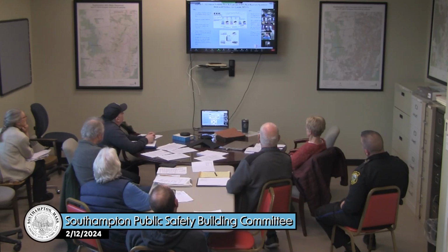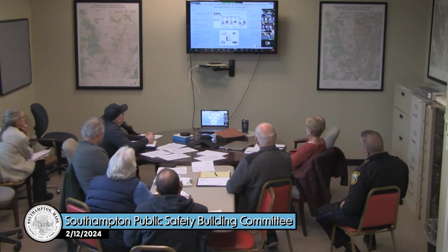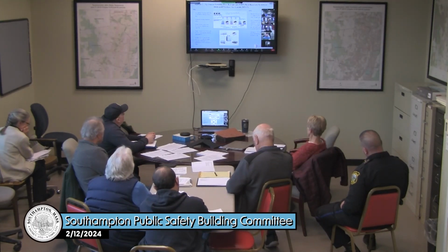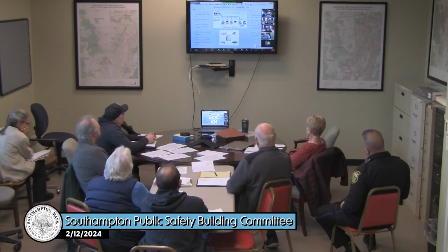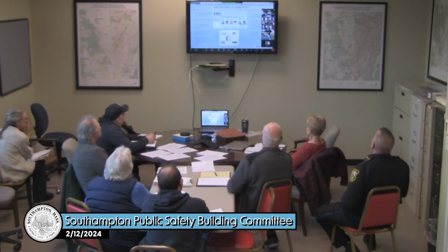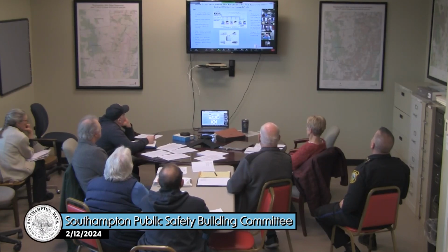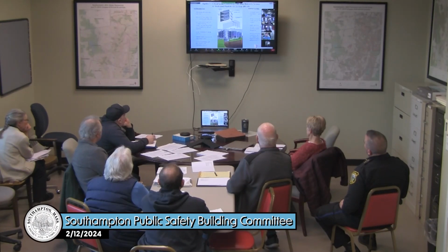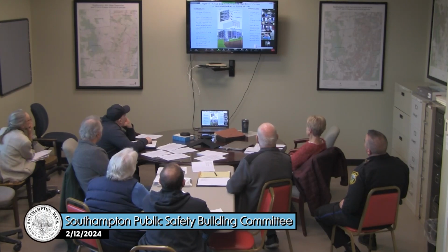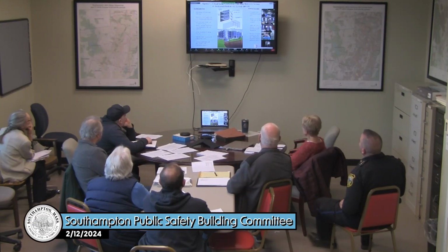And there will be refrigerant through the building. We do provide refrigerant leak detection. So if there ever were a refrigerant leak, it doesn't happen often, but if it were to happen, the detector will sense that and shut the unit off and send an alarm to the BMS. And then maintenance will just have to go out and we'll have to resolve the leak. Next slide. And then option 3 is similar to option 2 with the exception that instead of doing an air-cooled VRF condenser, it would be tied to a geothermal well field.